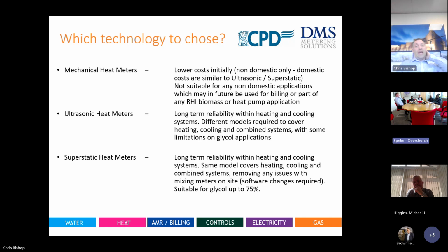So why do we choose certain cases? Like I say, we've discussed mechanical, ultrasonic and superstatic. Mechanicals are lower cost initially, but not suitable for any non-domestic RHI systems or any billing platform involving heat pumps. So what we're trying to say is that this is now a thing of the past for heat systems. Don't use them, don't specify them, use the correct keywords for your applications. Ultrasonic has long-term reliability within heating and cooling systems. As I said, no moving parts, very sensitive to flows and everything else, so no problem at all.